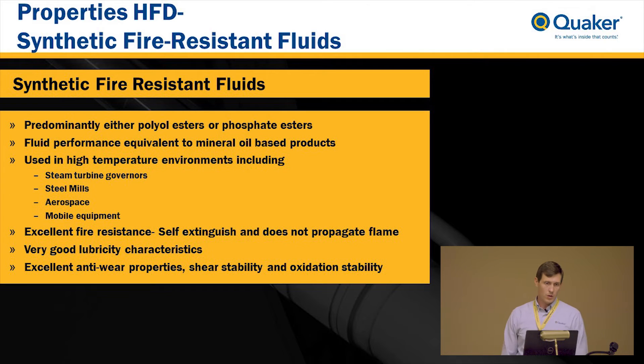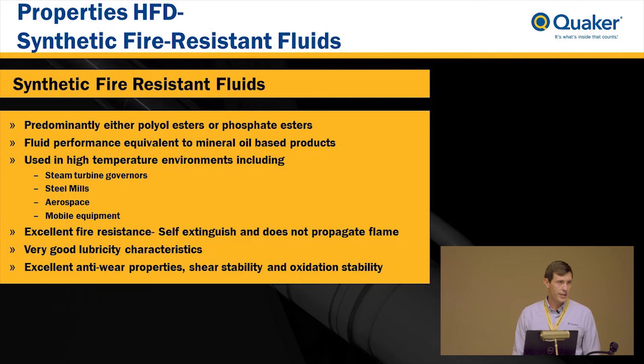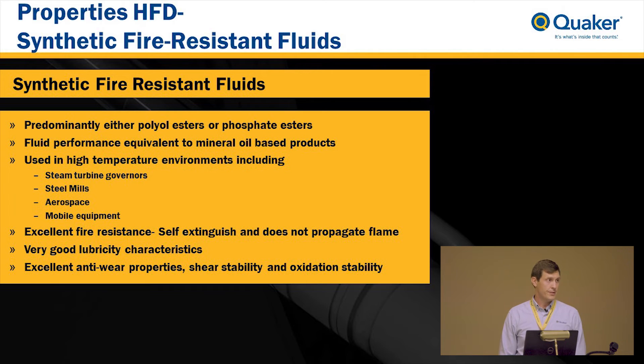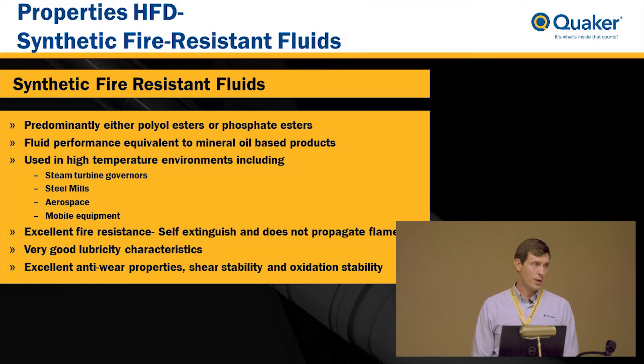The last category, where I wanted to spend most of my time, is the HFD products. This is the only one that does not contain any water — it's a synthetic ester based product. The two main categories are phosphate esters and polyol esters. These are a direct drop-in replacement for any mineral oil based hydraulic fluid and you can get it in any ISO grade you want. Benefits include being extremely fire resistant, biodegradable, and having the same properties as mineral oil based hydraulic fluid. It can also be used with the same elastomers, so there's no issue with seals.